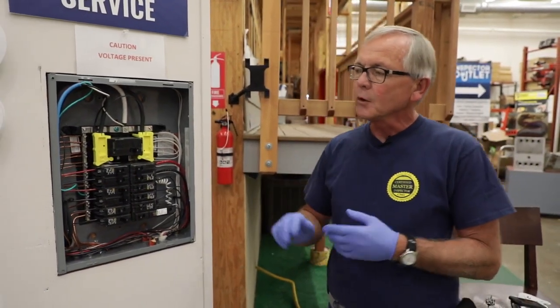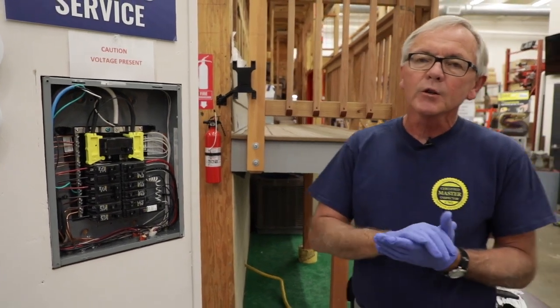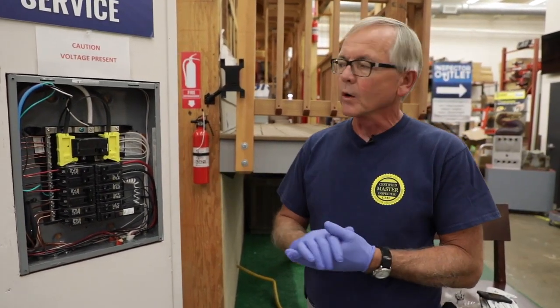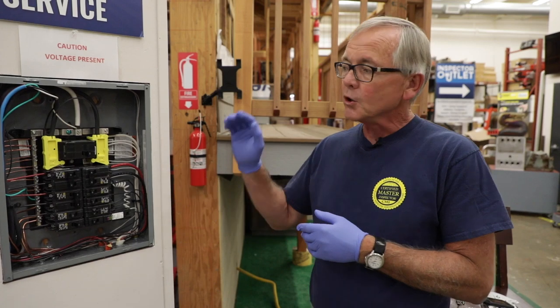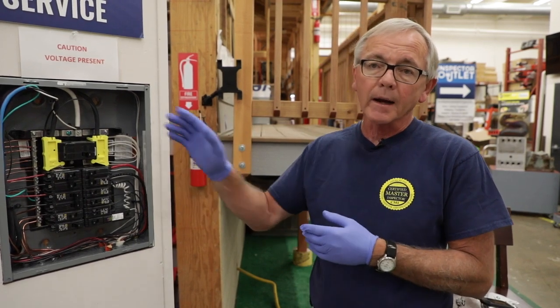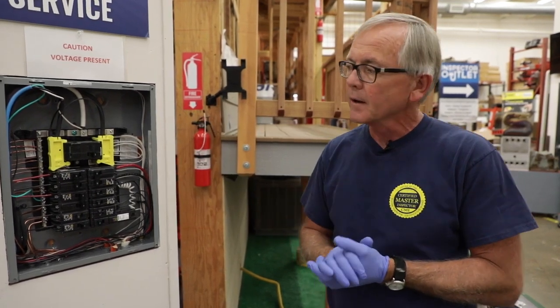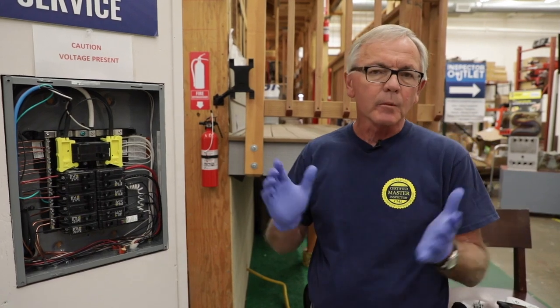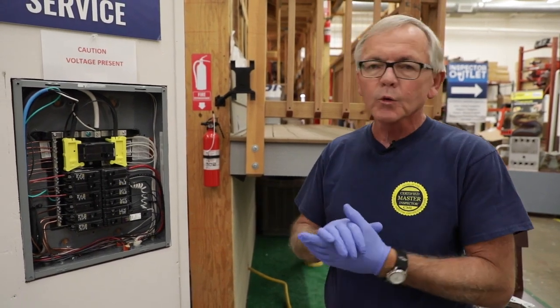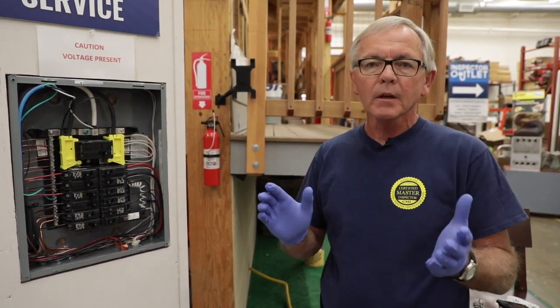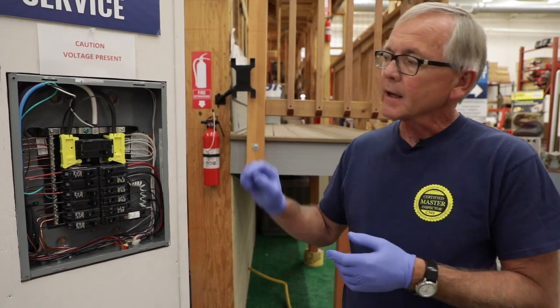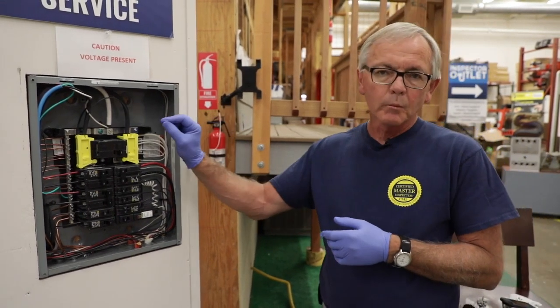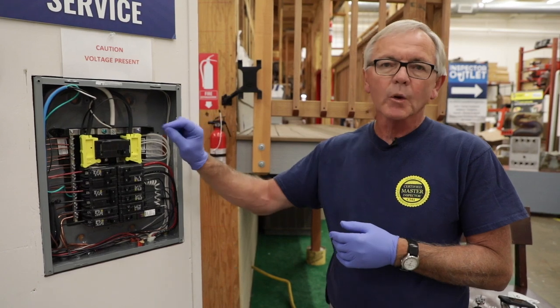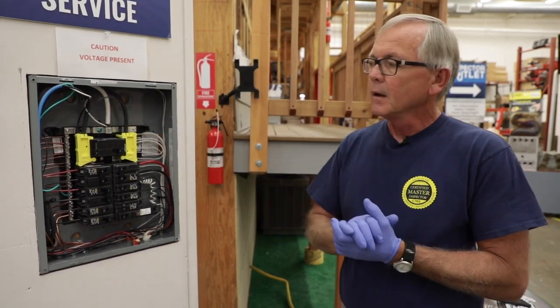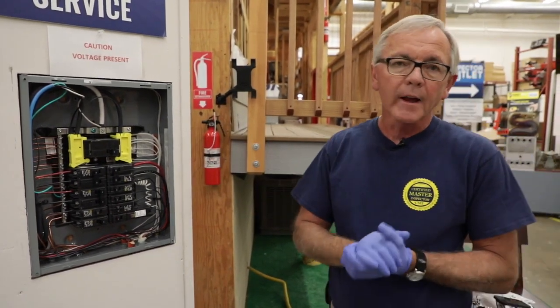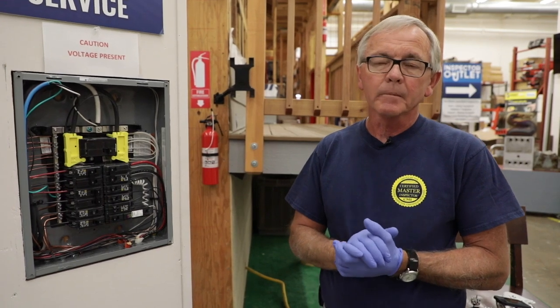However, from time to time, you may get into a real busy panel where it's full of wires and you can't see something in the back that you want to take a closer look at. The one thing I've done is I've fashioned my own little tool. I've got a 12-inch long, half-inch thick wooden dowel that I can use to just push wires from one side to the other so I can see behind. And I would not move these wires more than half an inch of travel either way.